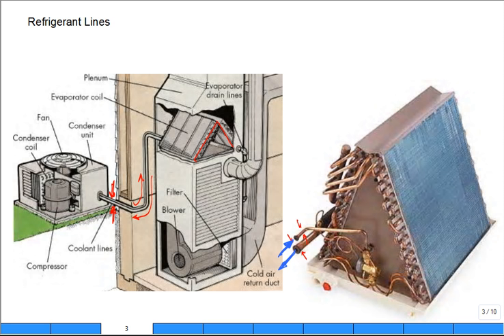Now, if you can trace this right here, it goes over and it goes into this right here. This is a restriction. That's our expansion valve. Now, it's got a control to it, and it's a TXV, thermostatic expansion valve. It's got a little bulb of a temperature sensor that goes over here and measures the temperature on the suction line, and then it says, oh, I'm coming out too warm. Give it more refrigerant. I'm coming out too cold. Less refrigerant goes in. So, it is some control mechanism. It's not electronic. It's just mechanical. They're old. They've been around for a long time. They're switching a lot of this stuff to digital, electronically controlled metering to that A-coil.